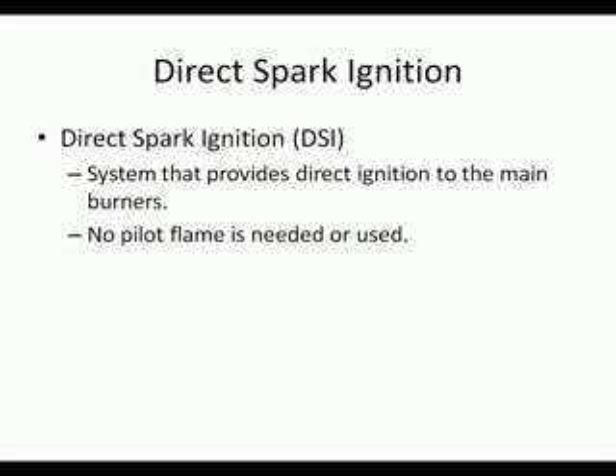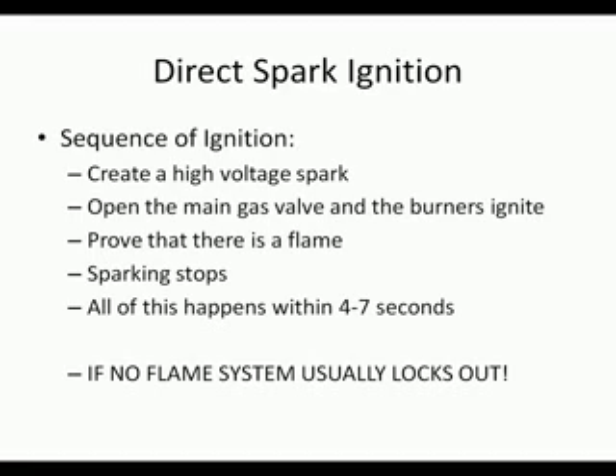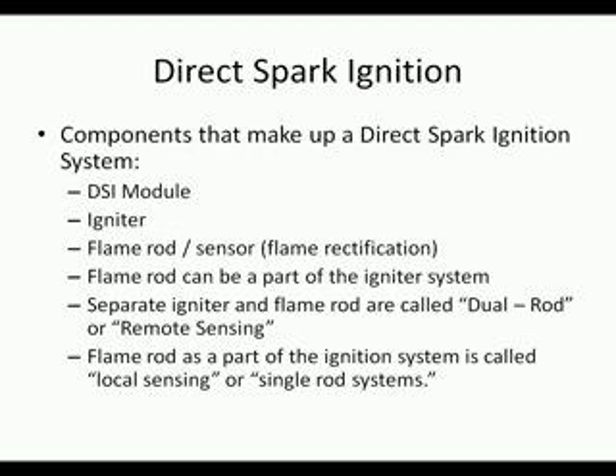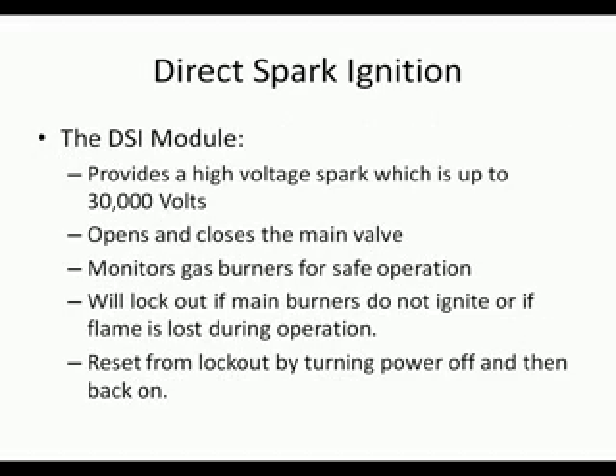The next type of ignition is direct spark ignition. You don't see this much in residential, but mainly on rooftop units. The direct spark ignition provides direct ignition to the main burners. No pilot flame is needed or used. It creates a high voltage spark, opens the main gas valve, and the burners ignite. It proves that there's flame, the sparking stops, and all of this happens within 4 to 7 seconds. If no flame, the system will lock out and force a service call.